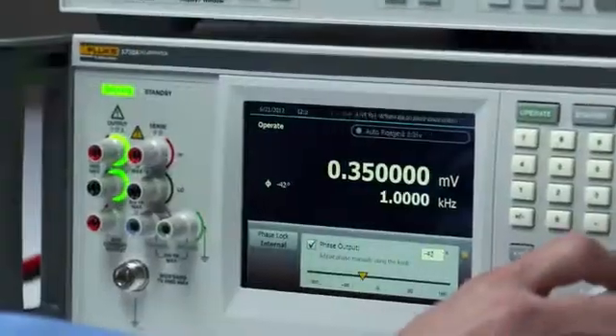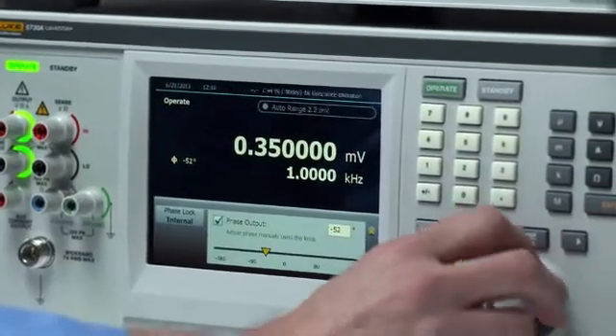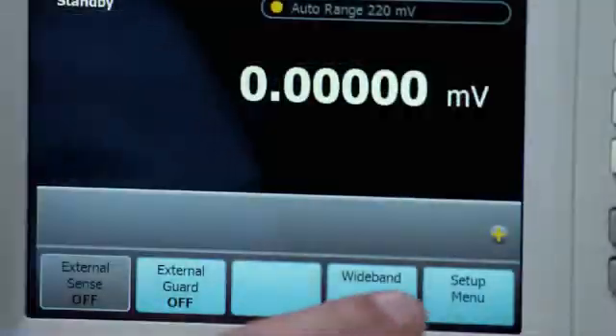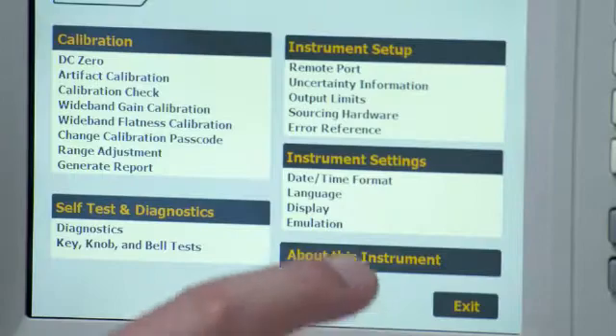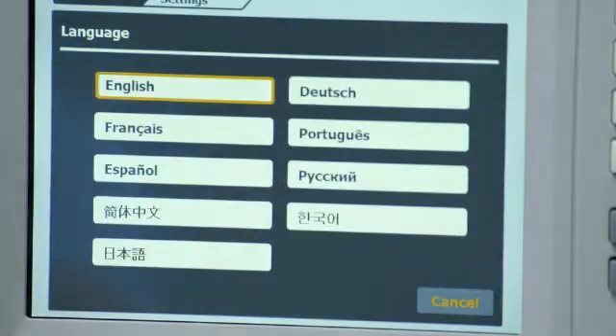The new front panel design combines the familiar keypad of the 5720A with the new 6.5-inch full-color capacitive touchscreen display. Now you can easily see functional outputs, calibration settings, and calibrator status in your choice of nine languages.